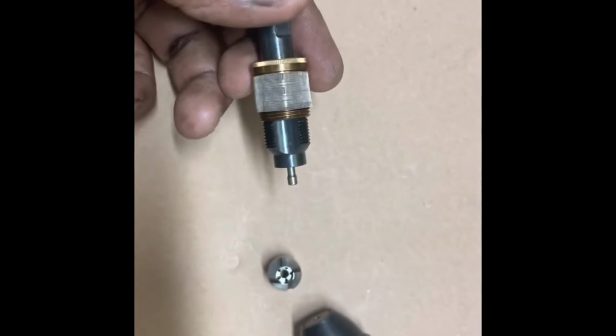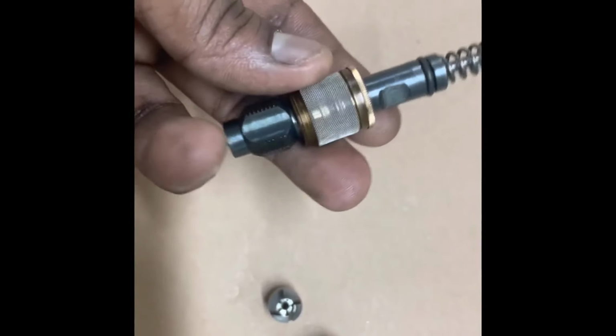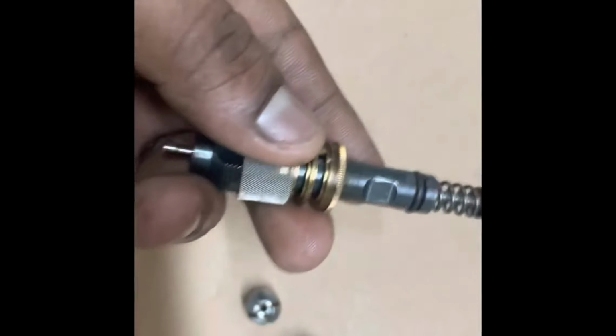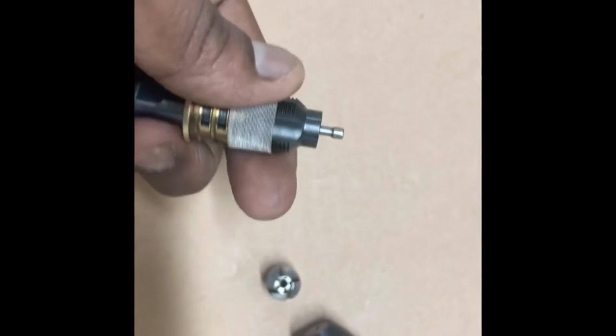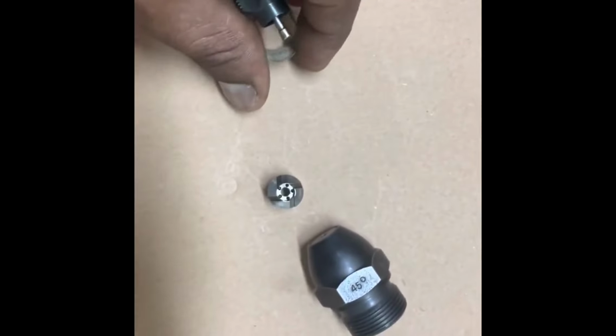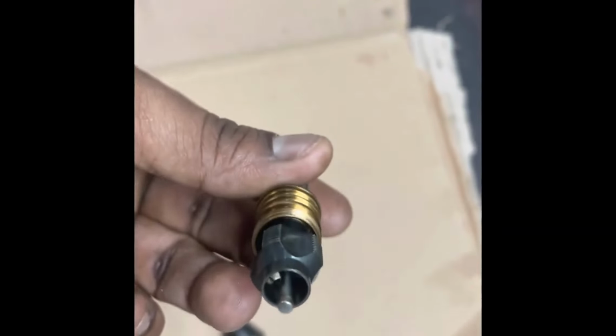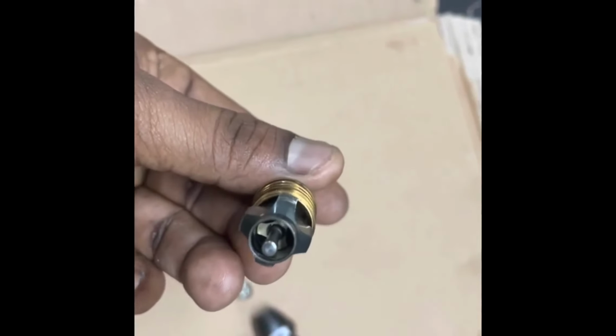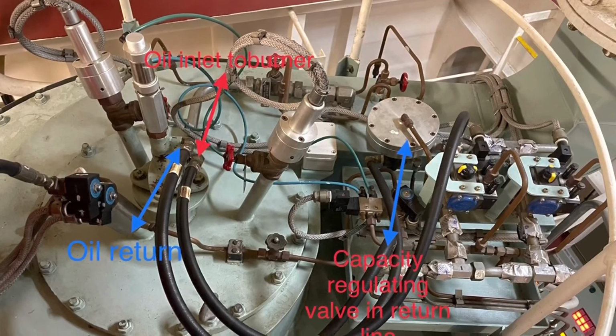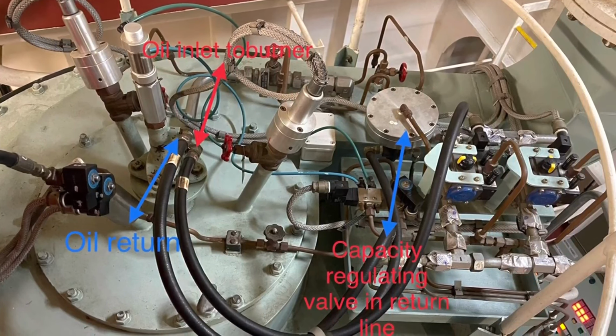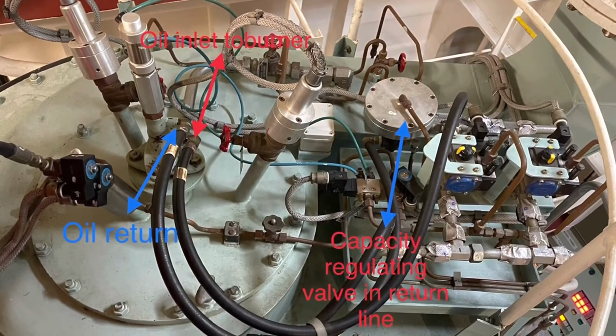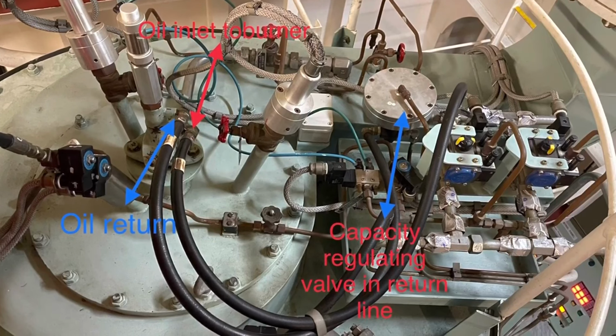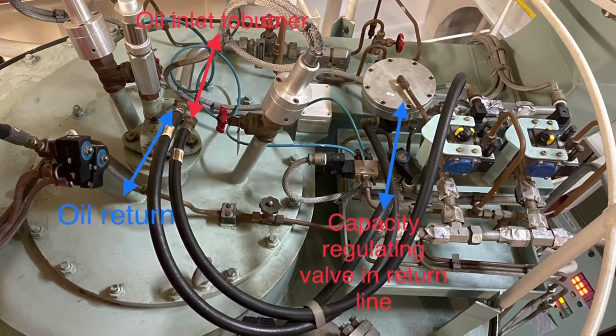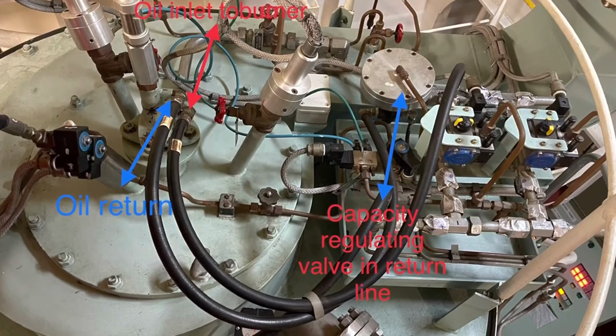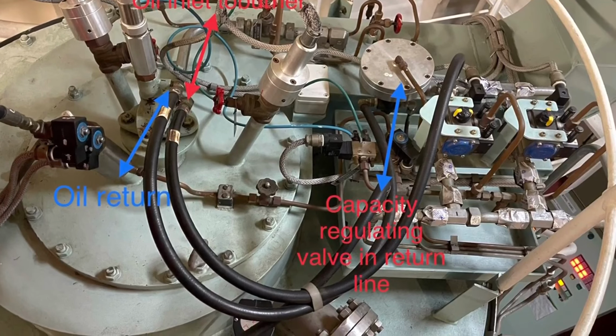The oil nozzle, as mentioned, is bypass type, which means in the return line a pneumatically controlled capacity regulating valve is mounted. When this capacity valve closes, pressure increases in the return line, which means higher oil quantity to the burner. So at maximum capacity of the inert gas generator, the return line is almost closed and no oil returns to the tank. So all the oil from the fuel oil pump goes to the burner.